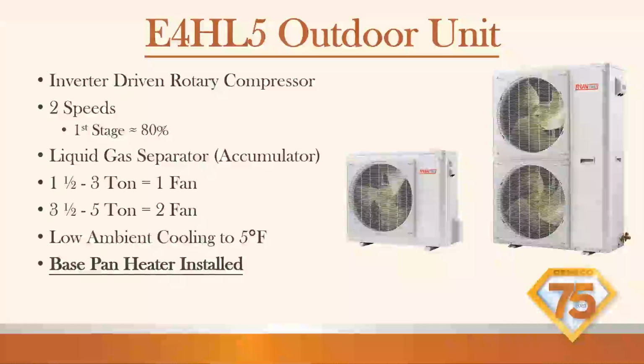100%, then it goes to the outdoor unit and it's calling for full stage compressor at 100%. But there's an inhibitor in here or algorithm that does not allow the second stage compressor to come on for 20 minutes because it's trying to be as efficient as possible. So it will not allow that compressor to kick on. And the only way you can tell that is through taking amp draw.